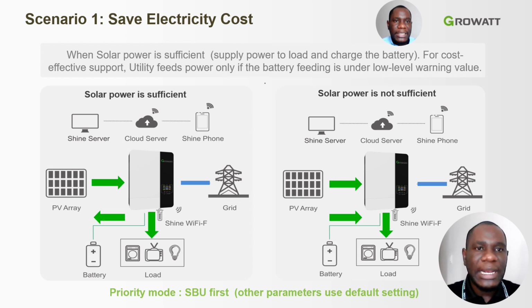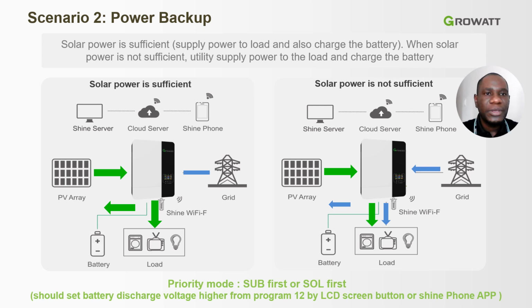For example, if the client wants to save electricity, then when solar power is sufficient, supply power to the load and charge the batteries as well for cost-effective support. And utility feeds power only if the battery is under the low level warning value. In that way, you are saving your electricity bill. Then we have the backup power mode. In this mode, if the solar power is sufficient, you supply power to the load and also charge the battery. When the solar power is not sufficient, then utility supplies power to the load and charges the batteries to make sure that you always have power backup in case of a fault or a grid outage.